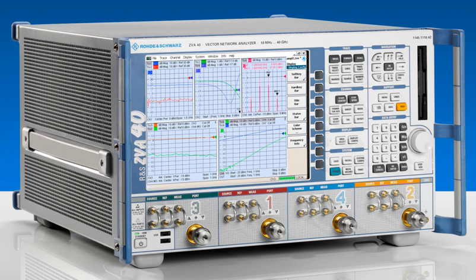Topic: Network analyzer verification kits. A number of verification kits are available to verify the network analyzer is performing to specification. These typically consist of transmission lines with an air dielectric and attenuators. The Agilent 85055A kit includes a 10 cm airline, stepped impedance airline, 20 dB and 50 dB attenuators with data on the devices measured by the manufacturer and stored on both a floppy disk and USB flash drive. Older versions of the 85055A have the data stored on tape and floppy disks rather than on USB drives.